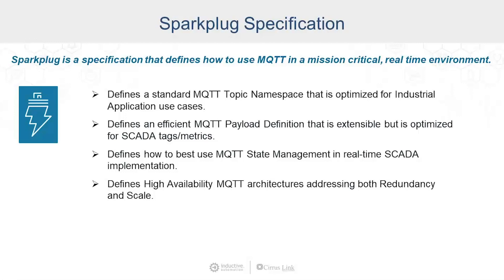Sparkplug defines a standard MQTT topic namespace that's optimized for industrial application use cases. It defines an efficient MQTT payload definition that's extensible but optimized for SCADA, tag, and metric representations. It defines how best to use MQTT state management in real-time SCADA implementations. And lastly, it defines some high-availability MQTT architectures addressing both redundancy and scale.